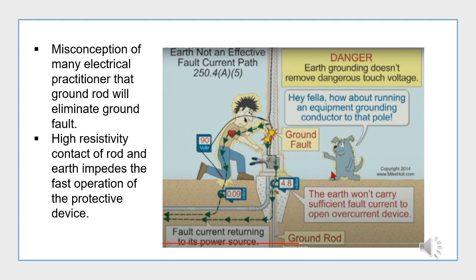There is a misconception among many electrical practitioners that a ground rod will eliminate ground fault. But due to the high resistivity contact of the rod and earth, this impedes the fast operation of the protective device. In the picture shown, the installation is provided with a ground rod which is connected to the extraneous metallic part of the system. Without the third wire or equipment grounding conductor, the protective device will never operate when there is an insulation failure. Any human or animal who touches or makes contact with the metallic part of the pole will become a current path to ground back to the source.